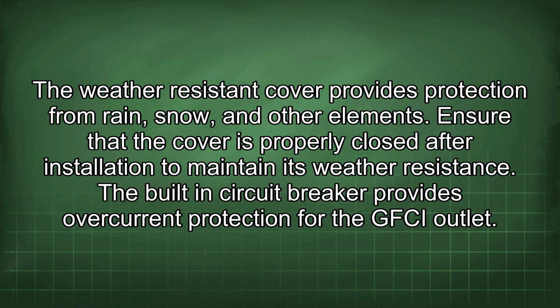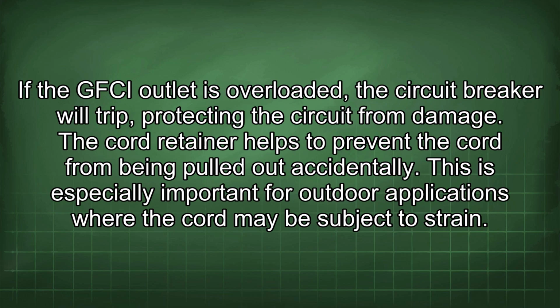The built-in circuit breaker provides overcurrent protection for the GFCI outlet. If the GFCI outlet is overloaded, the circuit breaker will trip, protecting the circuit from damage. The cord retainer helps to prevent the cord from being pulled out accidentally. This is especially important for outdoor applications where the cord may be subject to strain.